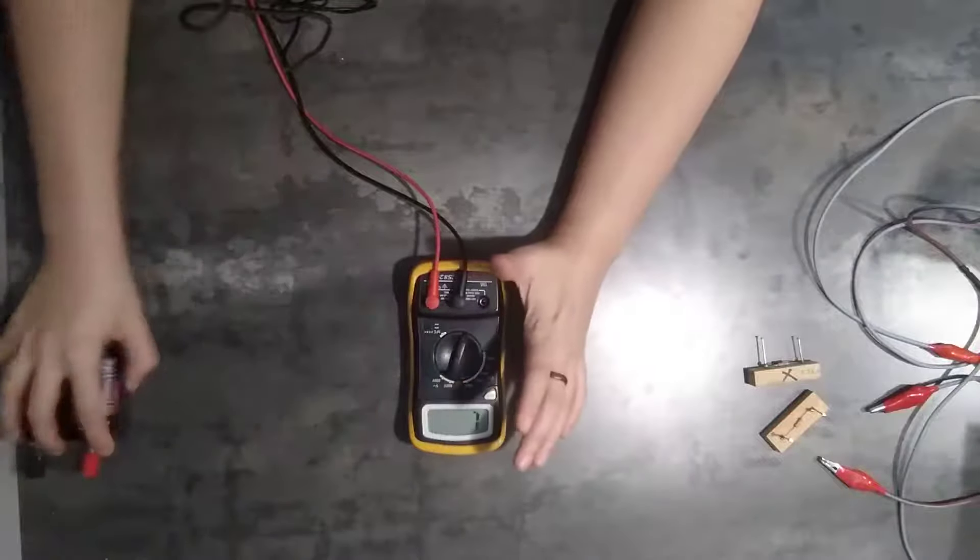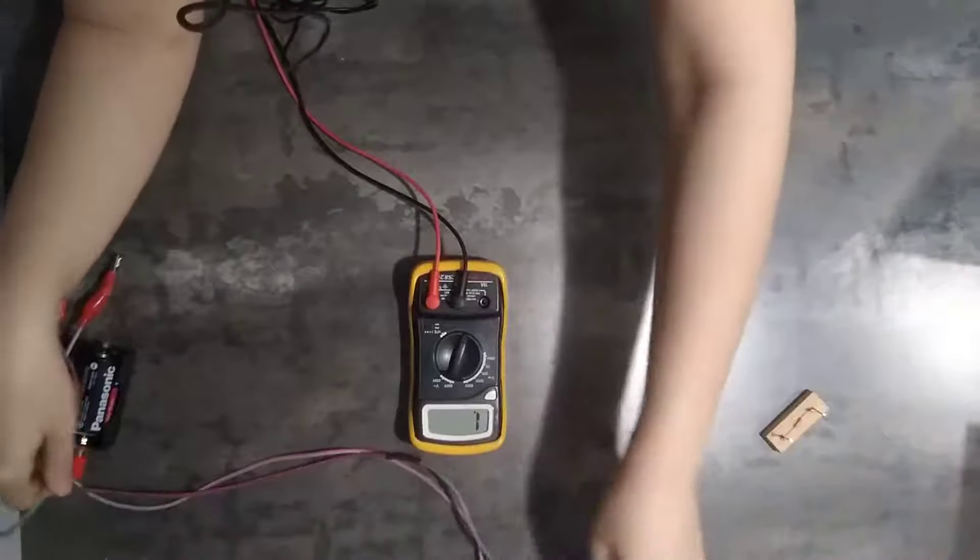So check this tool. Make sure this tool is working. That this one you can use already. Then use this because you are sure that this one will work. Check all the connecting wires. If we give you 8 connecting wires, you check all the connecting wires. Resistance should be 0. So you turn the knob to resistance. To be 0.